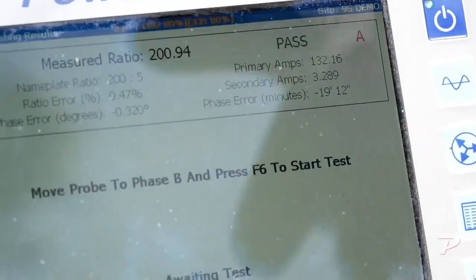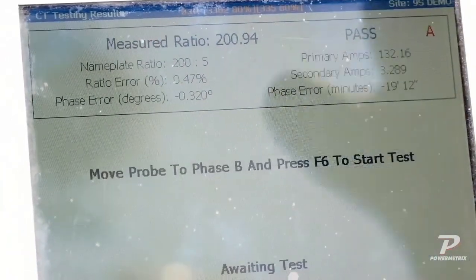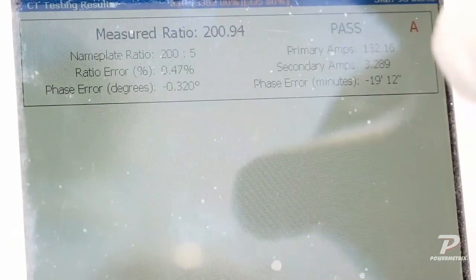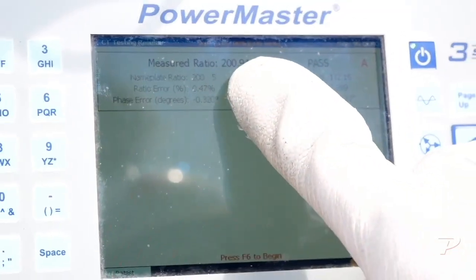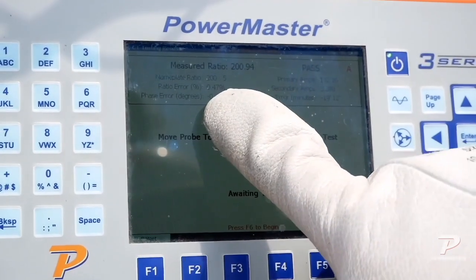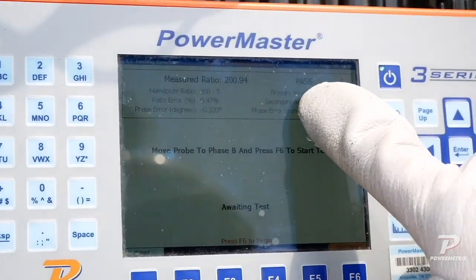Because he had all that right, we didn't get a cross phase, meaning he wasn't on the wrong phase, and we didn't get a polarity reversal, meaning his probe wasn't backwards or the label away from the load. Since everything was correct, the load also measured well, so we only got 0.47 on our ratio error. So we got a pass here in green, everything looks good.